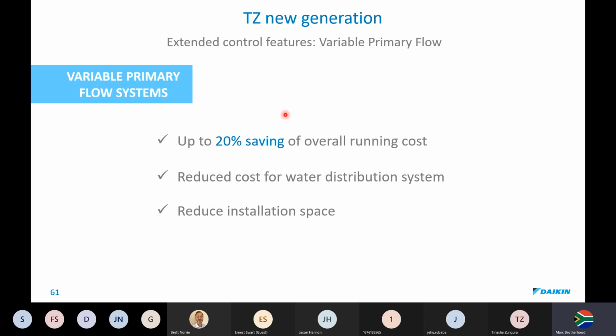So what is the advantage of variable primary flow systems? Well, up to 20% saving on the overall running costs, because besides your chiller running, which cycles on and off, your pump never switches off. So your pumps actually are responsible for a lot of energy consumption on the site. People think it's the chiller. Believe me, your pump is your silent killer on your energy bill. So if we alter the speed of the pumps, it's going to be a big energy saving for you, which is ultimately a reduced cost for your water reticulation and reduced installation space by reducing piping designs and configurations.